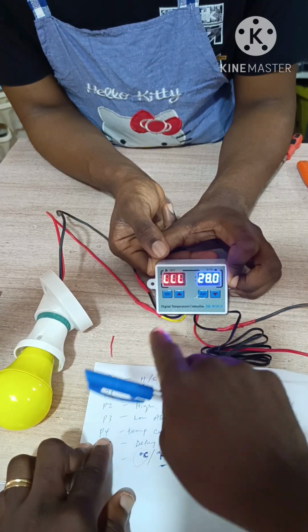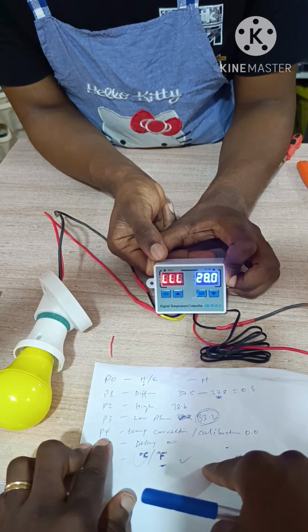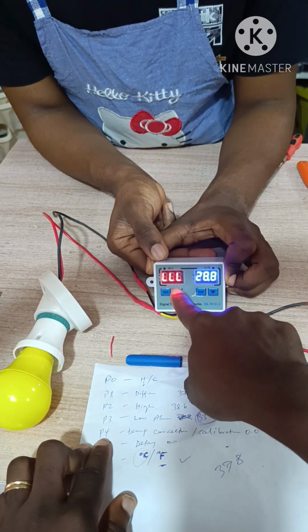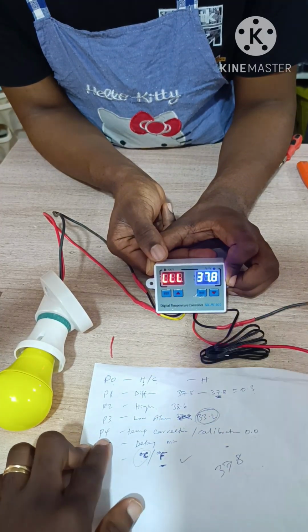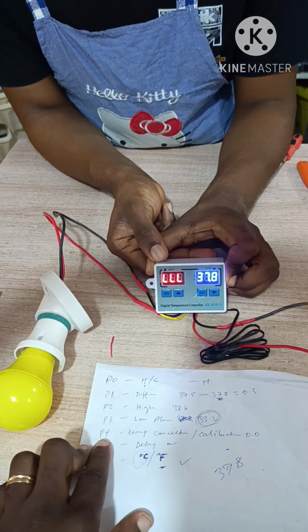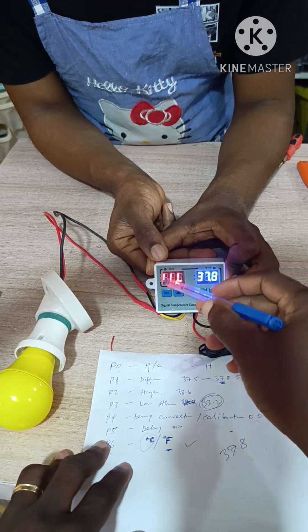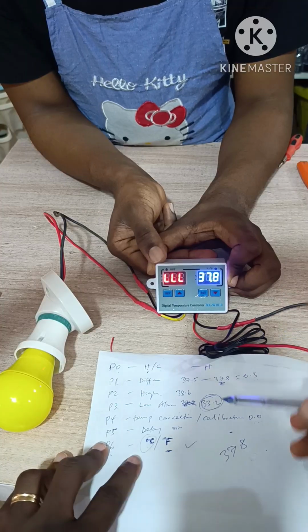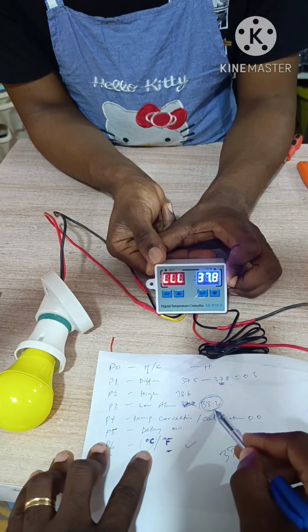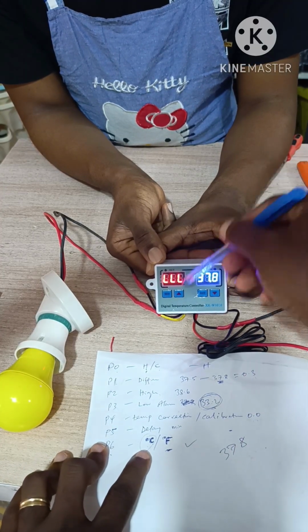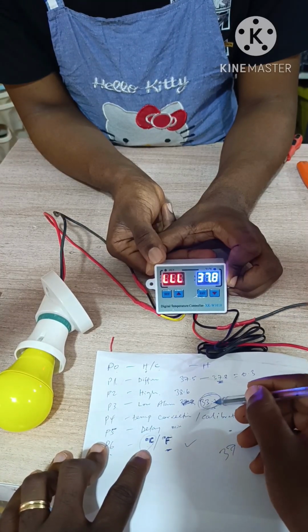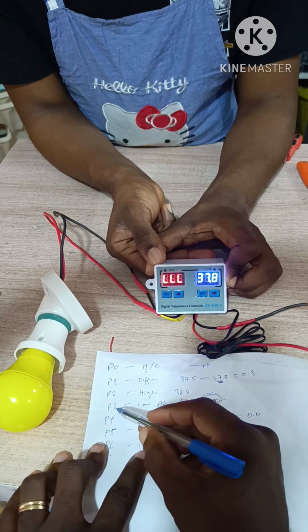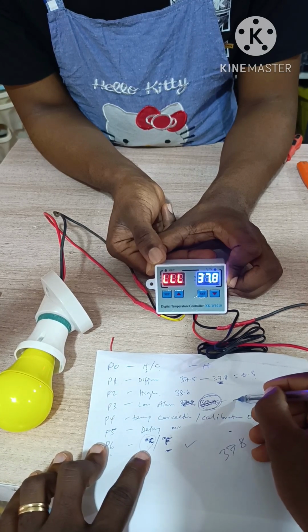So I'm going to set the set temperature. You press once, it will be blinking, then you increase it, 37.8. Okay, so this is the set temperature I want. Now this is just telling you that your temperature is low. Because we set it to 33.2, so it means the room temperature is lower than 33.2. But for the purpose of the training, I'll bring P3 down to 20.